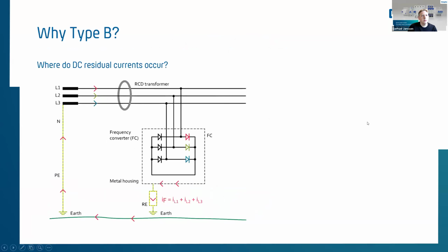Yeah, why type B RCCB or why type B RCD? Where do DC residual currents occur? So this is the standard description. You have a 3-phase load, 3 lines, and the earth, and you have a frequency converter involved in the whole system, which mostly gives us the problems of direct DC currents. This was one of the applications where type B RCDs were developed, in history.